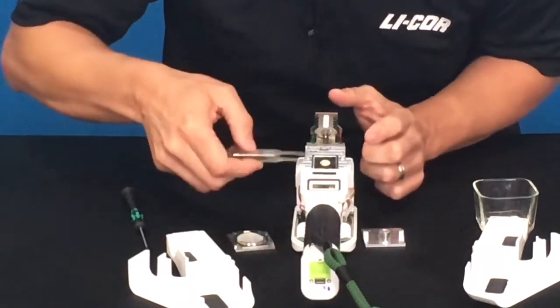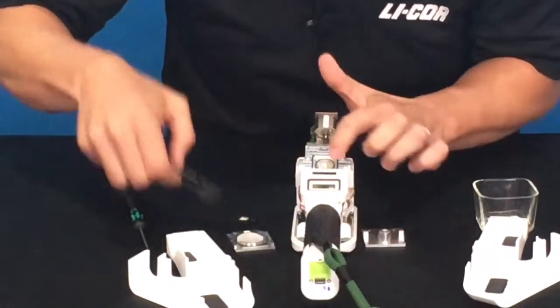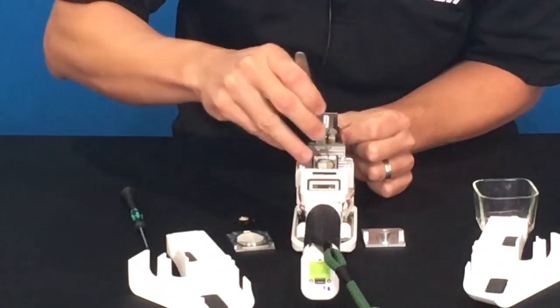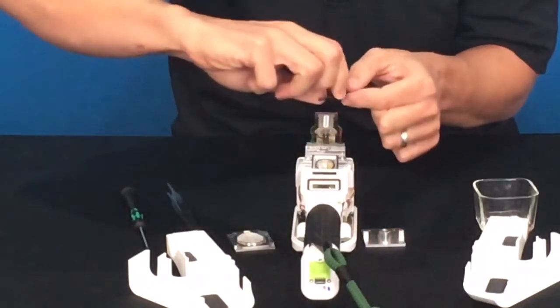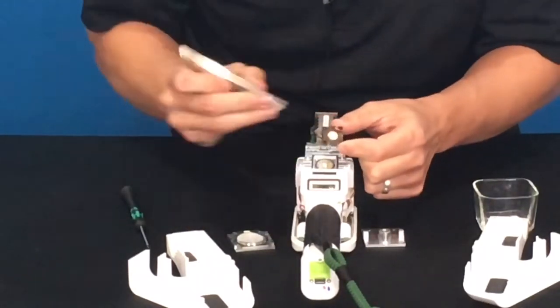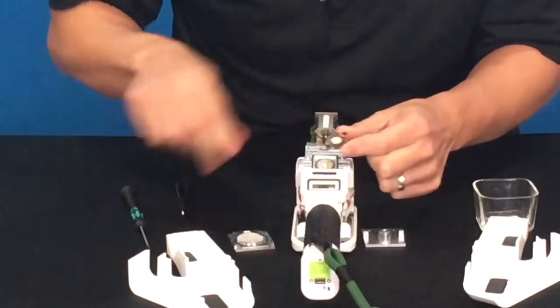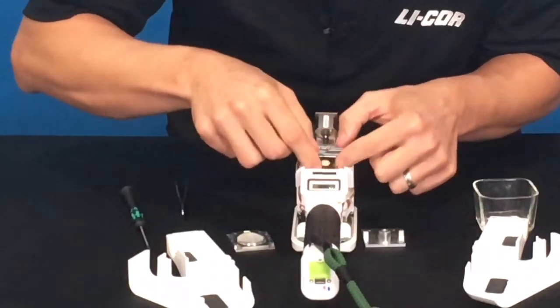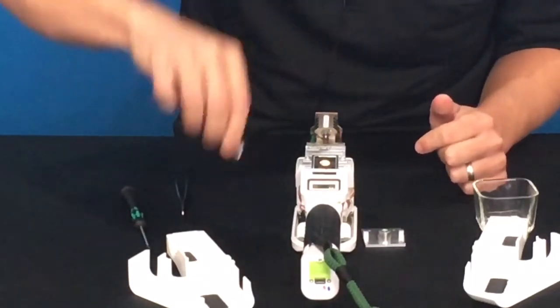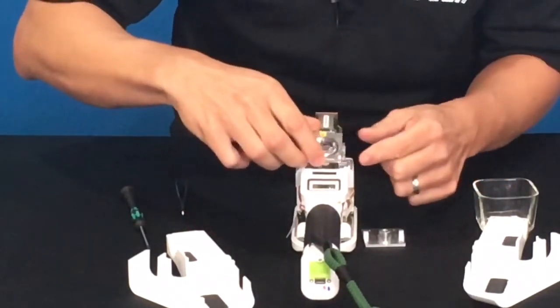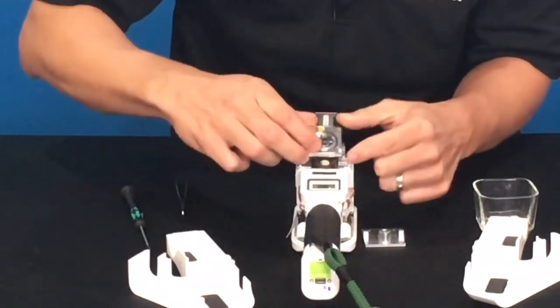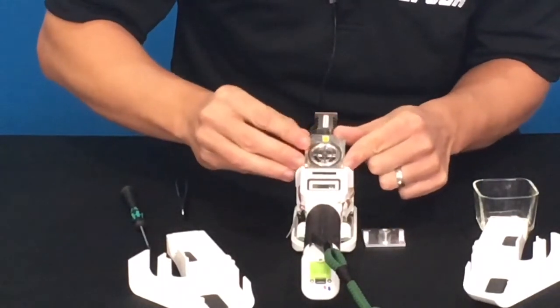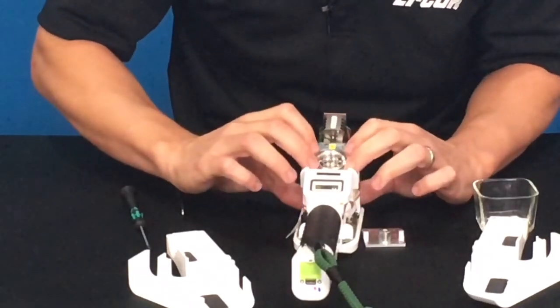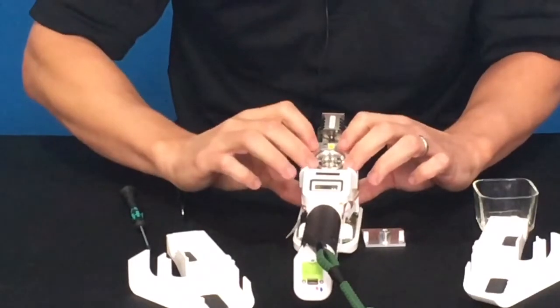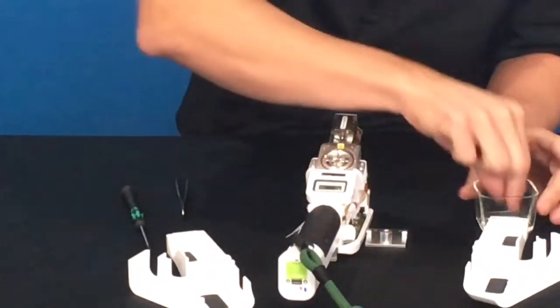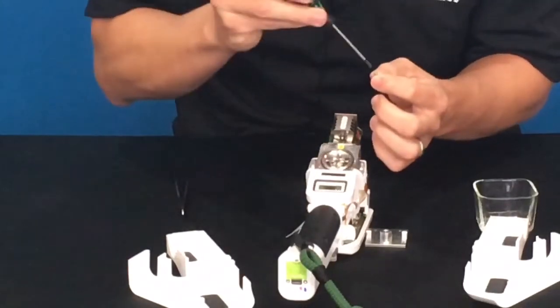There are pins in this component for two of the corners. There are two pins machined in here which need to align with the holes here and here in the pump. So those help you make sure you're lined up properly. So once you have it lined up properly, this part with the filter goes on next. And there are, again, pins to align everything. And here you just want to be careful that you are putting even pressure to push the pump evenly down on those pins. And so you would want to hold it in place and take your 4 Phillips head screws.